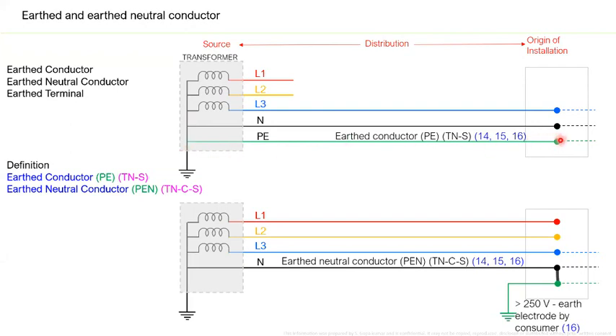So this is the earth for the whole power supply. The earth terminal at the consumer premise is connected back to the neutral of the source. So this earth terminal is called the earthed terminal. It's regulations 14, 15, and 16. The request or demand for an earthed terminal at the consumer premise is made by the electricity supplier. This is very, very important because you have a very low fault loop impedance path.